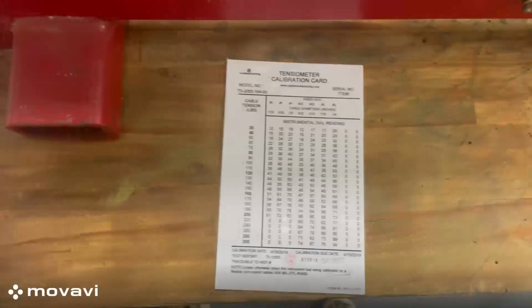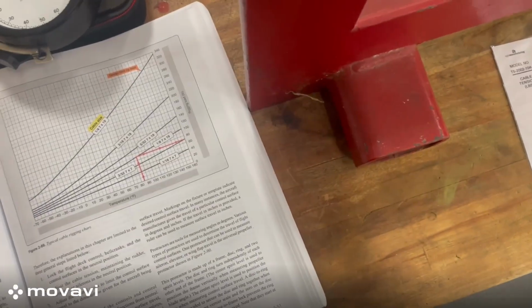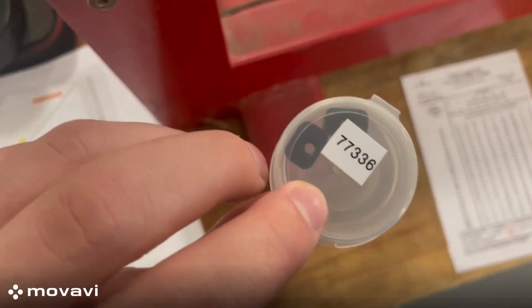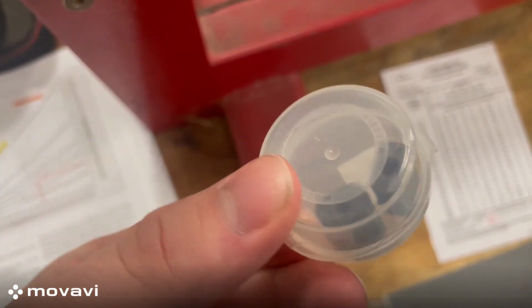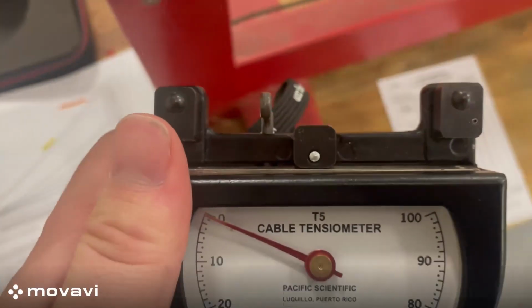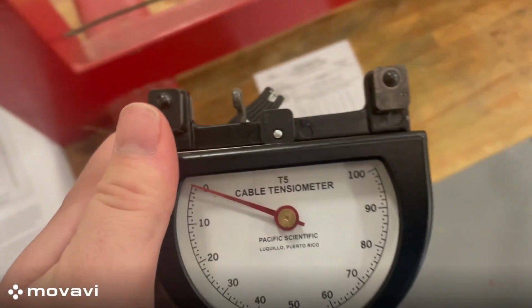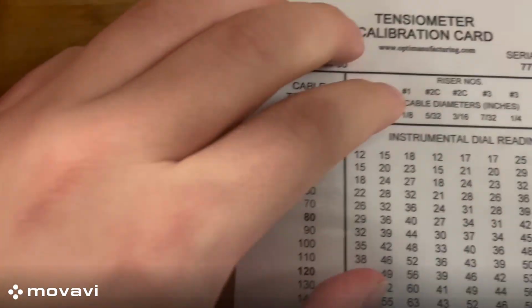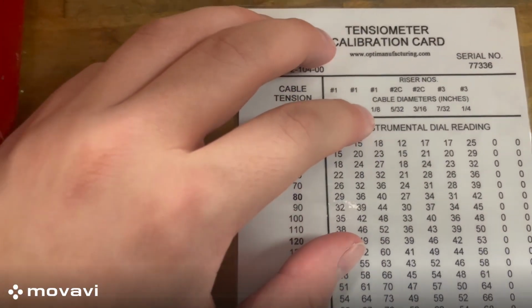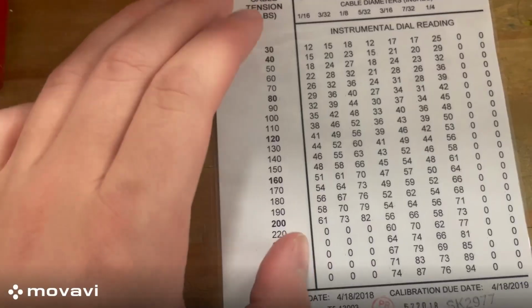Unfortunately, it does not stop there because our cable tensiometer does not read in pounds. So the first step is to figure out which riser block we need to use. You can see these are the riser blocks here. There's one already on it, and this is calibrated per your cable diameter. So we had a 1/8 inch cable, which uses a number 1 riser block, which luckily was already on there, but you can switch them out if you need to change them.